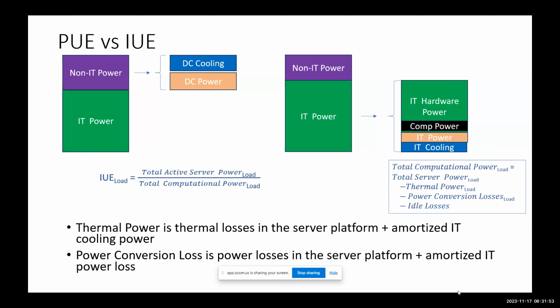Let me verbalize what I think you're saying, and then let me give you an answer. I think what you're worried about is, don't make me go to every little component and measure the idle for each of these. But my point is, if it's a data center, it's got X number of components that are unique and they're repeated multiple times to make the data center or the rack. If I know each one of those unique components, I know their idle power consumption, and so I can easily sum up and get the overall idle power.